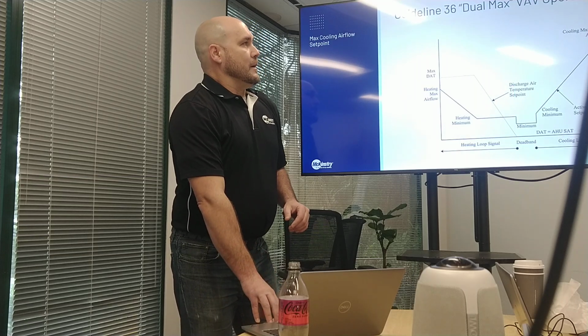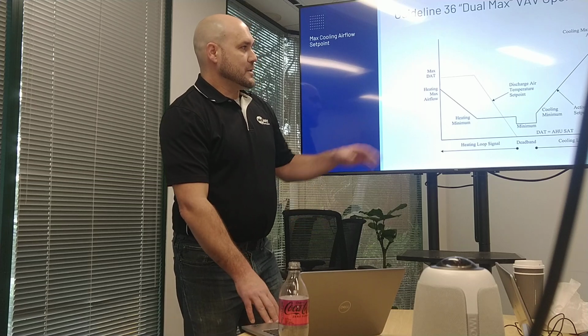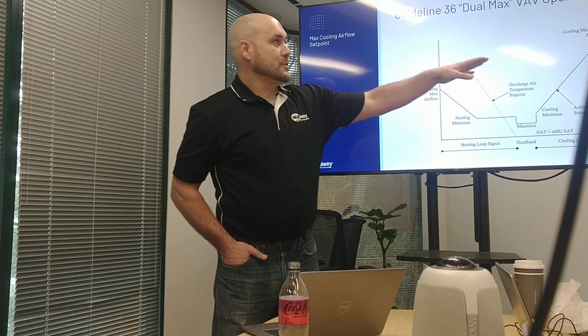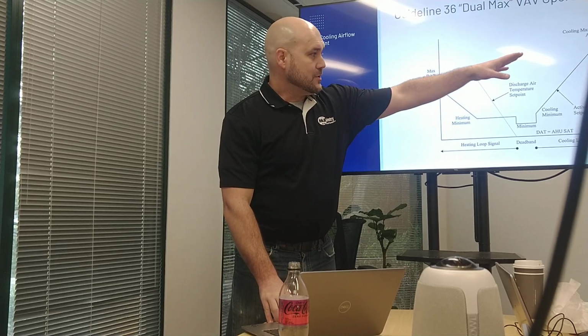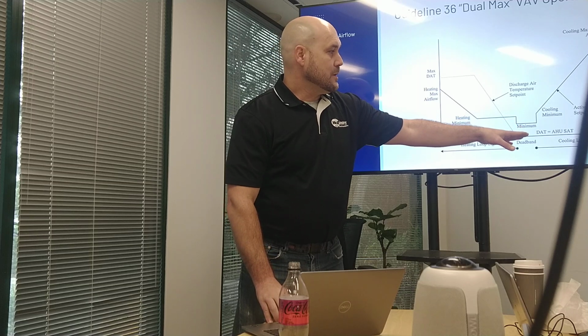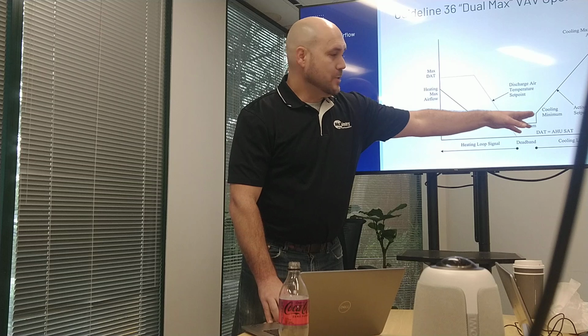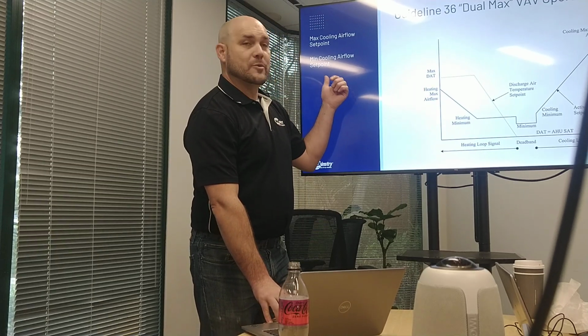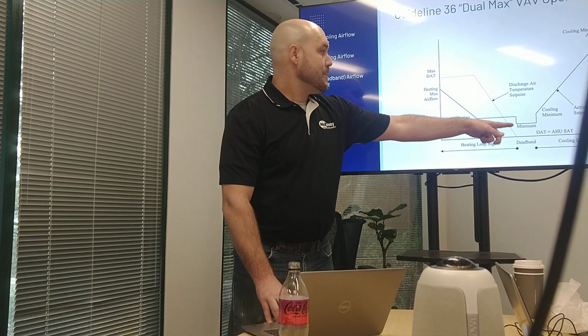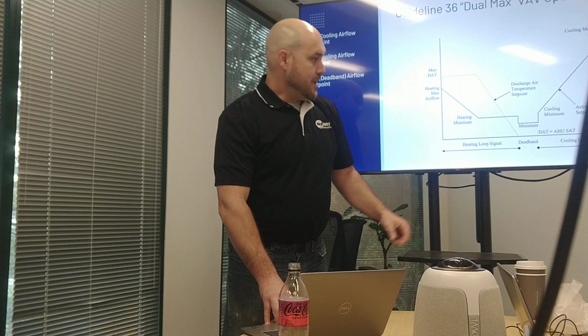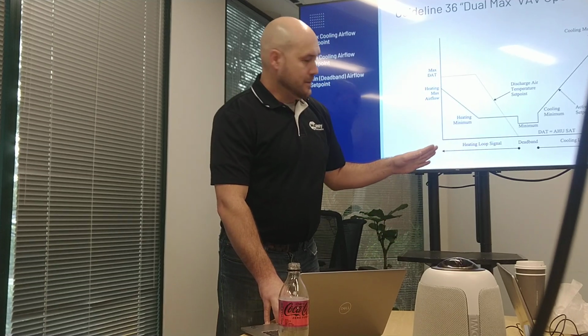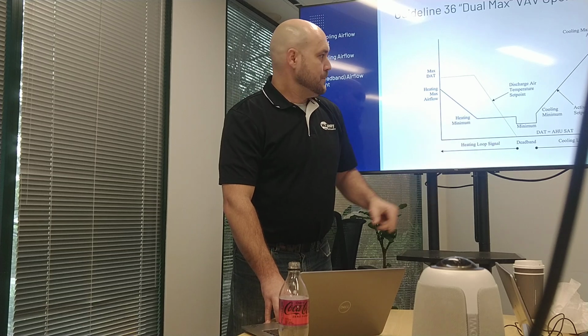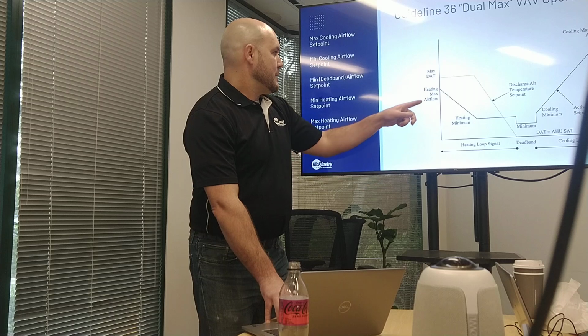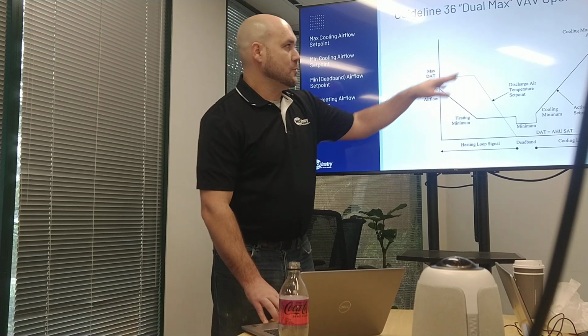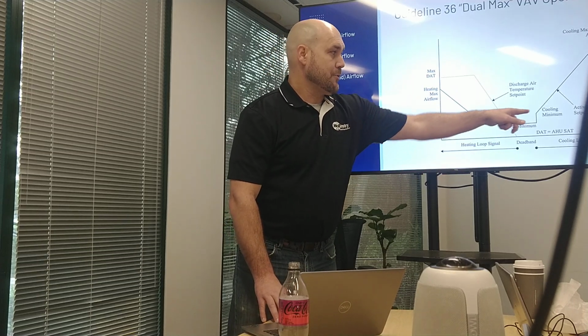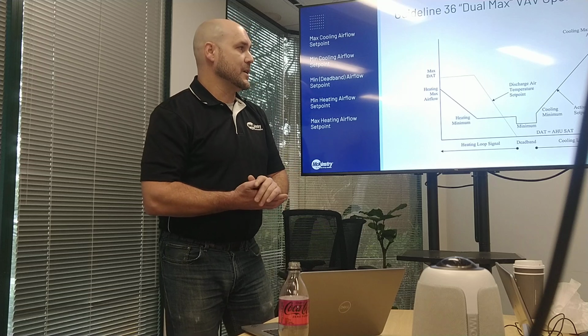state of the art. This is what is described in Guideline 36. So there's a lot more going on here. You still have the cooling maximum airflow in the top right. As you have less and less call for cooling, you come down to a cooling minimum. So you need to define the minimum cooling airflow. You need to define your actual deadband minimum, and then it steps back up again as you get into the heating regime, and you'll have a heating minimum, and then you also have a heating maximum. So they call it a dual max. There's a cooling maximum and a heating maximum, but there are also 3 different minimum values that need to be defined.